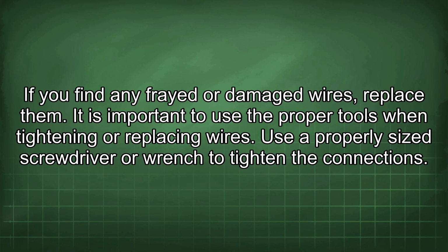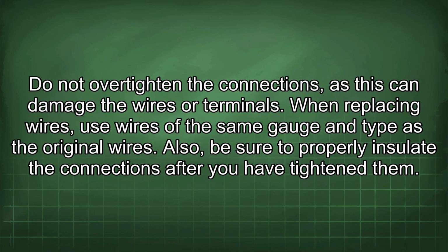It is important to use the proper tools when tightening or replacing wires. Use a properly sized screwdriver or wrench to tighten the connections. Do not over-tighten the connections, as this can damage the wires or terminals. When replacing wires, use wires of the same gauge and type as the original wires. Also, be sure to properly insulate the connections after you have tightened them.